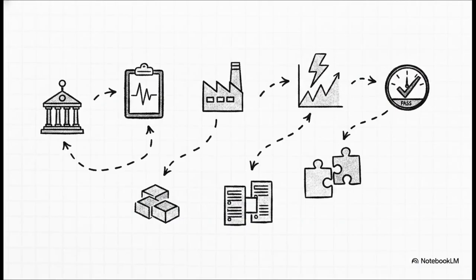Relying on a floor plan and looking at room names like ICU or surgery to size your power system, that's a recipe for disaster. Instead of just blindly adding up numbers, international standards actually demand this rigorous 7-step process. You've got to confirm local regulations, do a clinical risk assessment, dig up official manufacturer data, hunt down those hidden transient and peak loads, design your architecture, verify overall compatibility, and finally run rigorous tests. Remember, your power chain is quite literally only as strong as its weakest link.